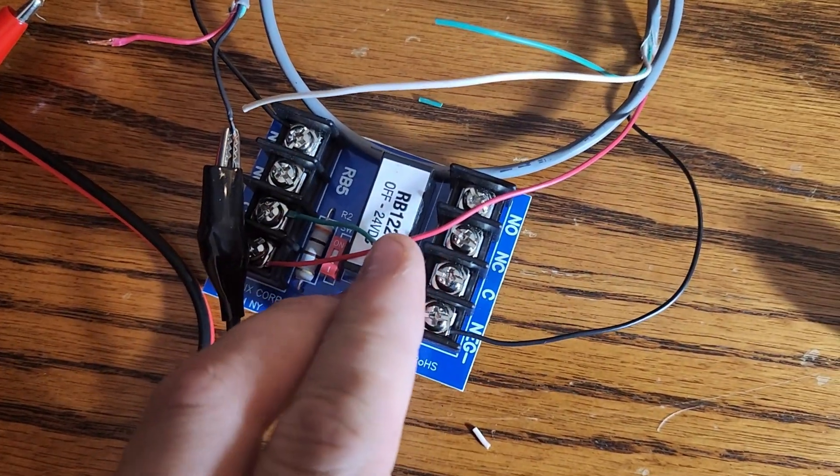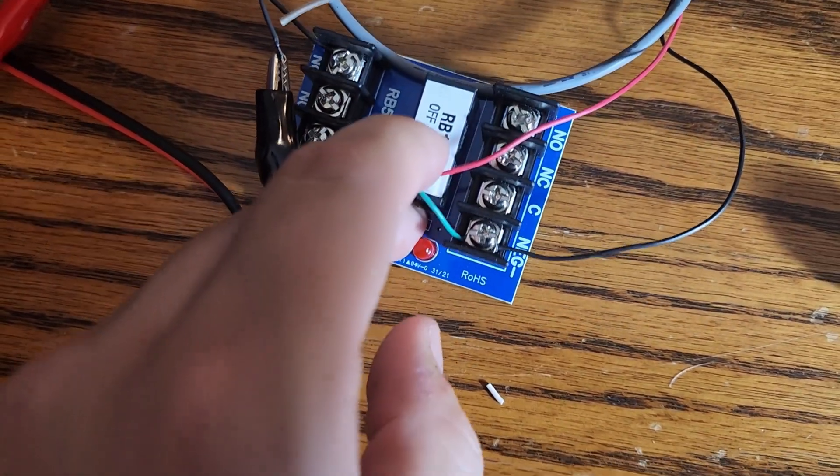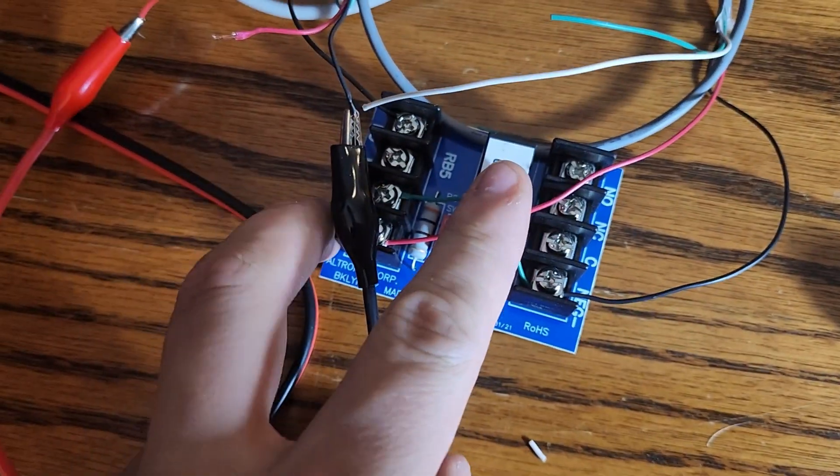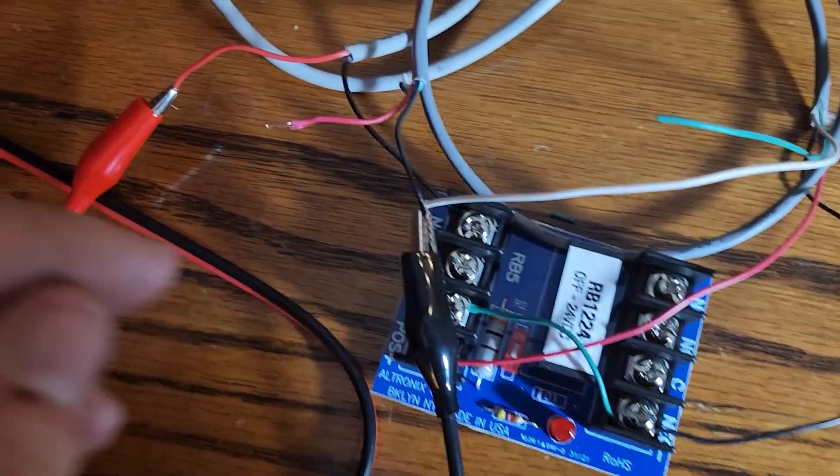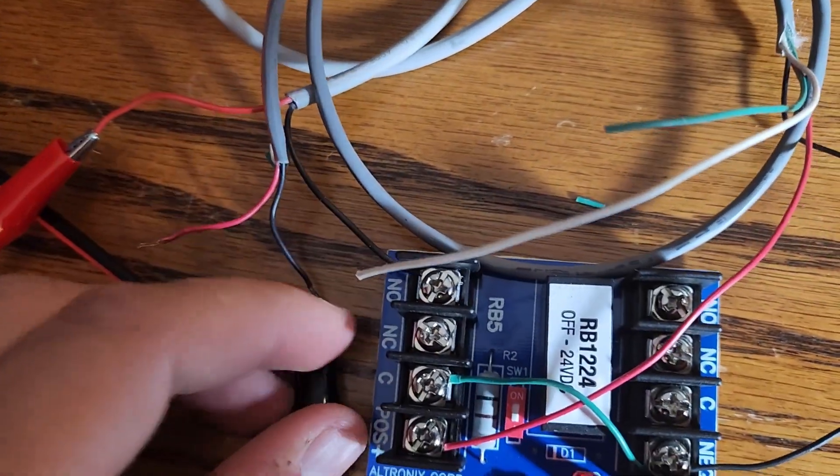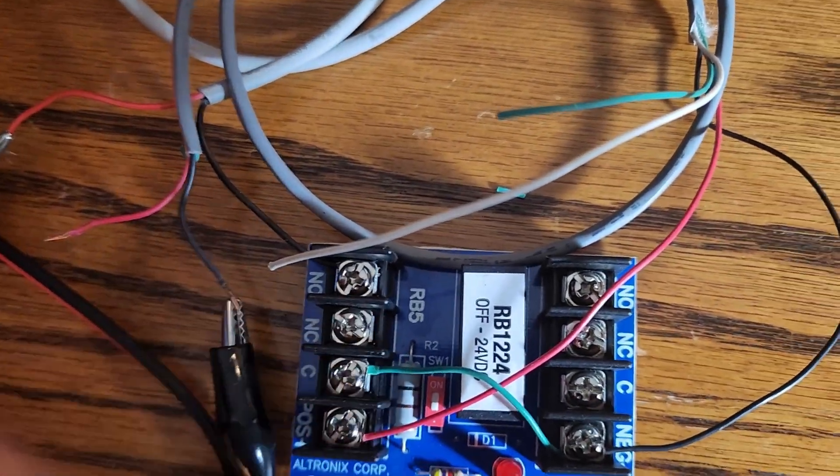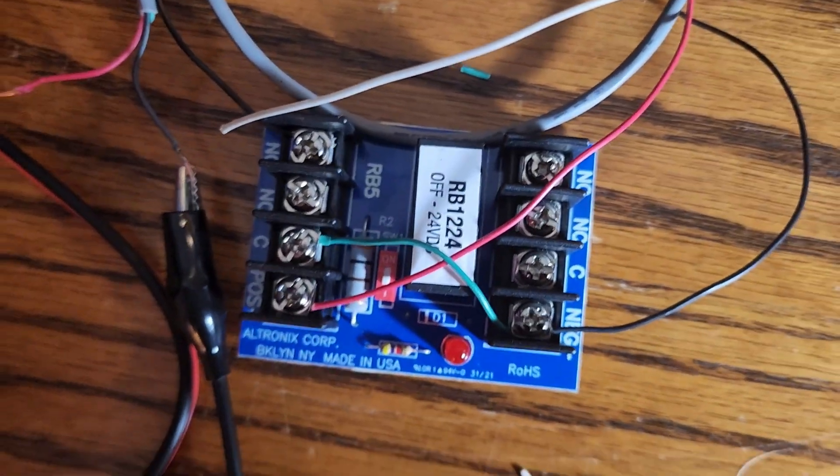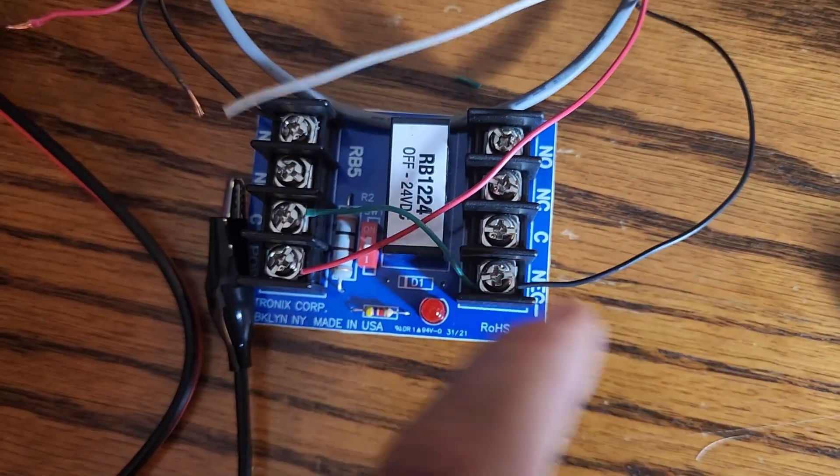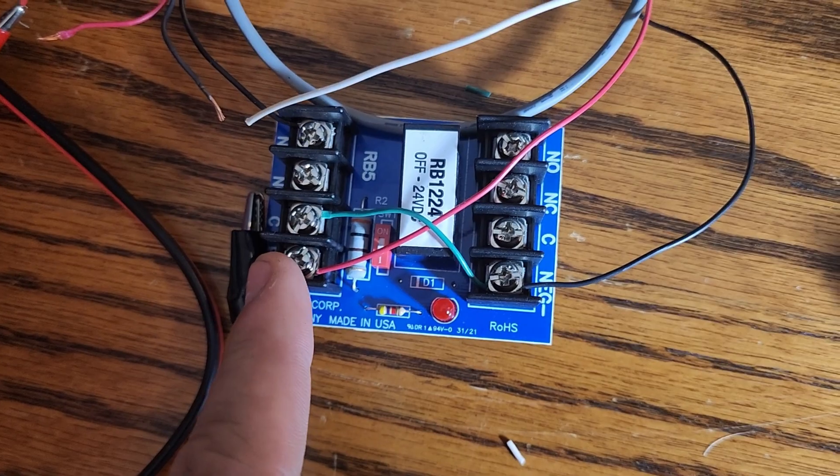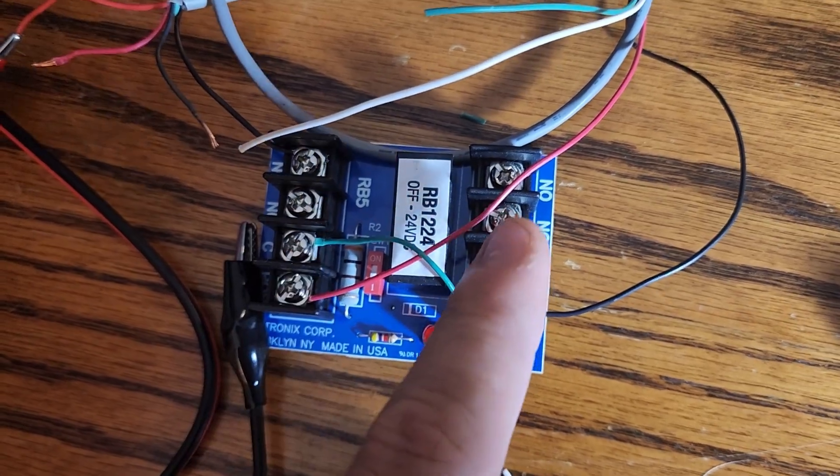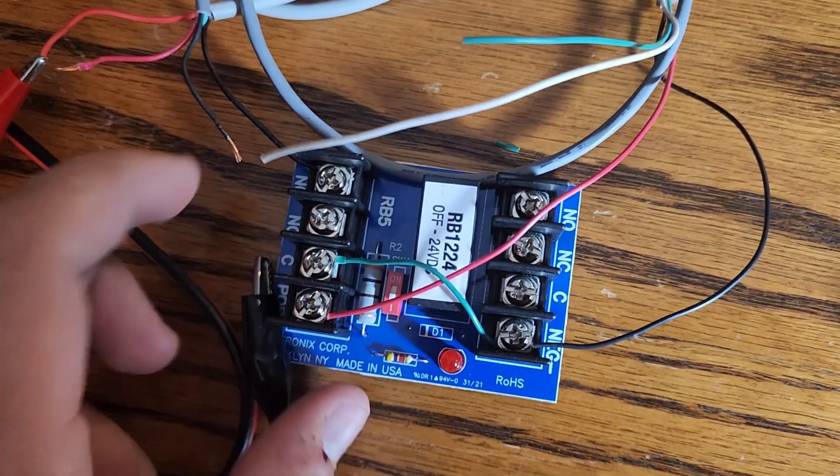I then have a jumper coming from my negative to my common. On the lock end, the negative of the lock, because we are doing a negative trip, not a positive trip. If we were doing a positive trip, we would want the jumper to be in the positive side or going back to our power supply, feeding the common.